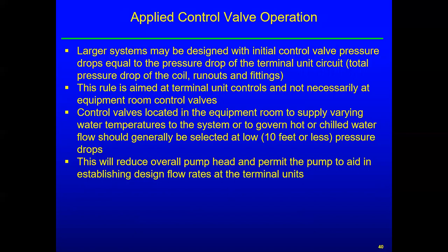This rule is aimed at terminal unit controls and not necessarily at equipment room control valves. Okay, so this is at the terminal unit where we're actually conditioning the space. Now, in the mechanical room, where we will have valves to control the amount of chilled water that's pumped or to distribute it out, we want to minimize the pressure drop on those valves. So control valves located in the equipment room to supply varying water temperatures to the system or to govern hot or chilled water flow should generally be selected at low, 10 foot or less, pressure drops. So, you know, this third bullet is in reference to design in a mechanical room, and the first bullet is at the terminal unit, which is actually conditioning the space. Big difference between those two. This will reduce the overall pump head and permit the pump to aid in establishing design water flow rates at the terminal unit. So just another comment on the fourth bullet is a comment on the third bullet.